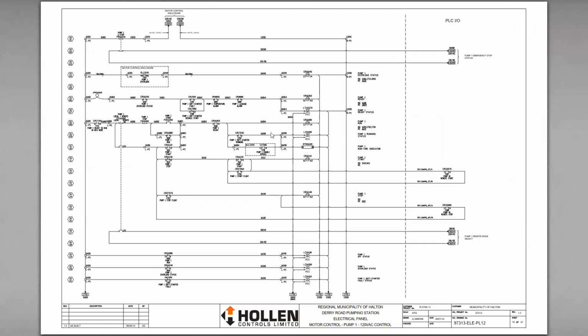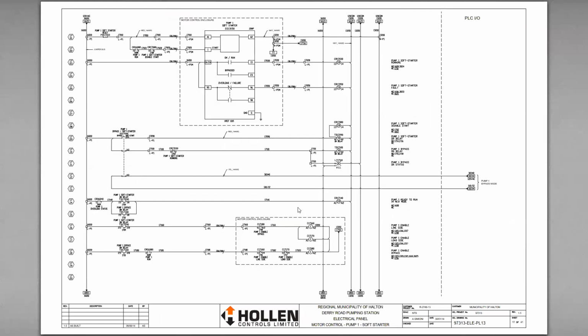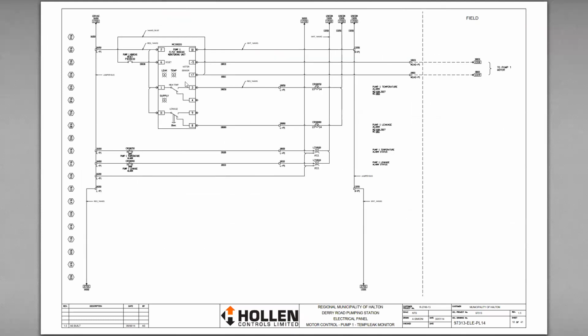You've got your hand-off-auto switch for the pump. So local-off-remote or local-remote is how they had it, with start and stop buttons, the seal-in circuit. Then you had your PLC run command and stop command. And then that circuit times 3 for all the different pumps.